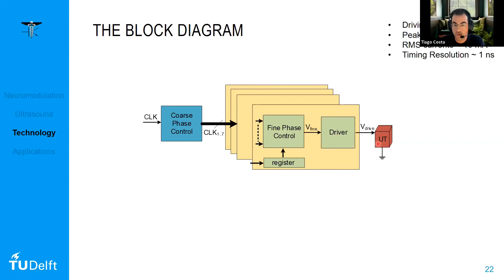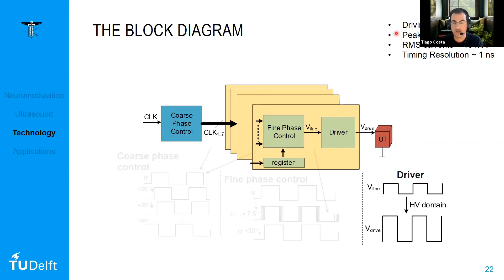And there's here an example of the clocks that are used. So from 0 to 180 degrees in steps of 30 are then sent to all channels. In each channel, there's a fine adjustment with a resolution of 7.5 degrees. And then the voltage is boosted normally to 20 or more volts, ideally, to achieve more pressure at the output. So you have here a few specifications that normally we want.